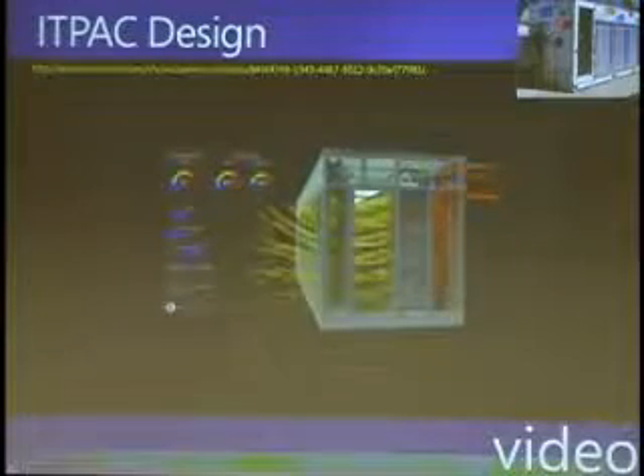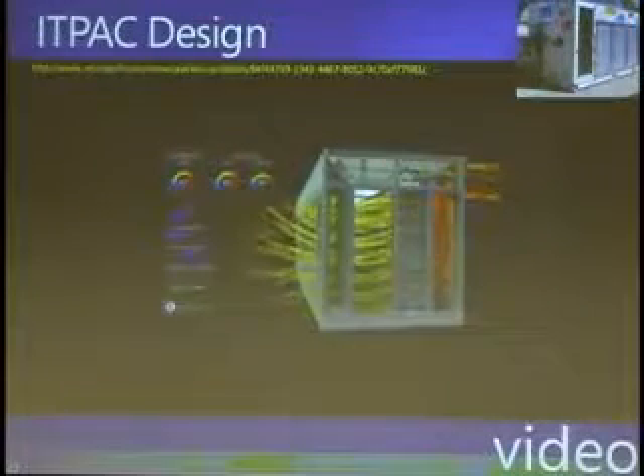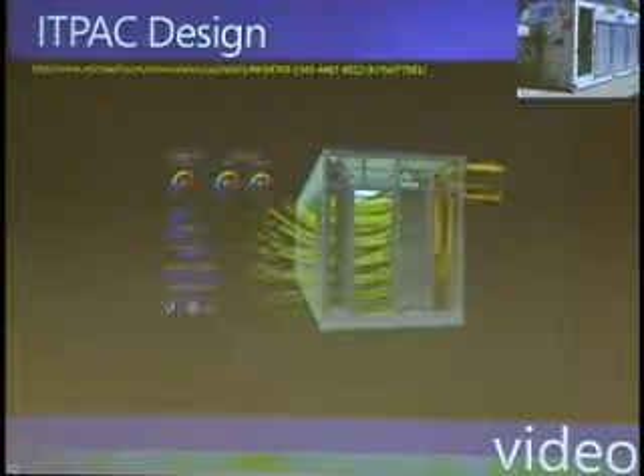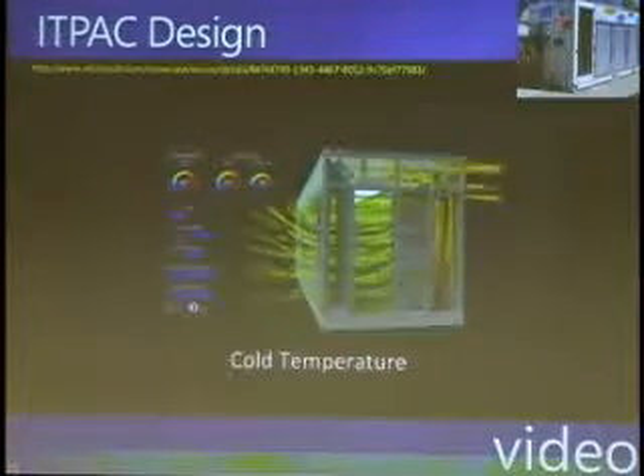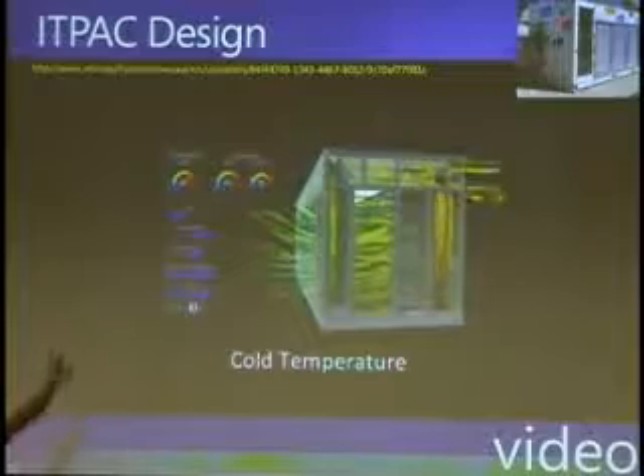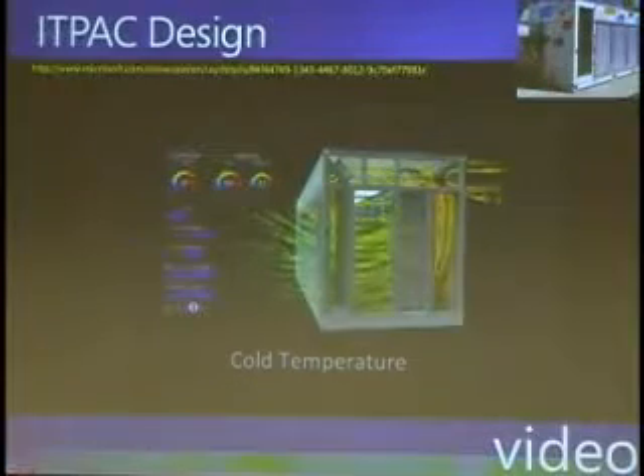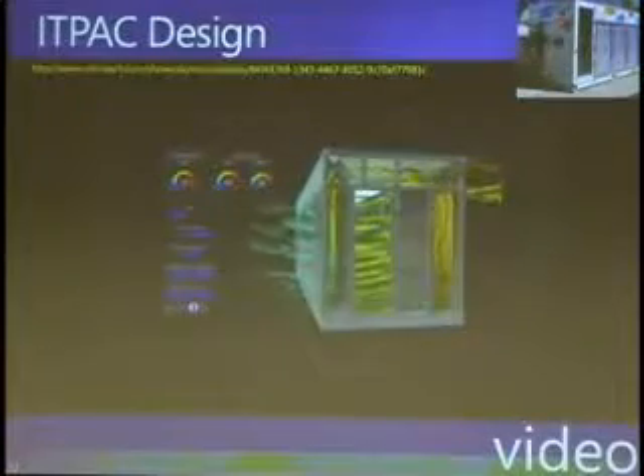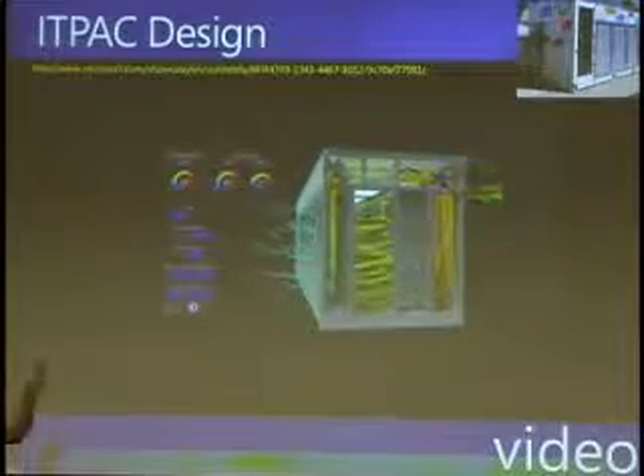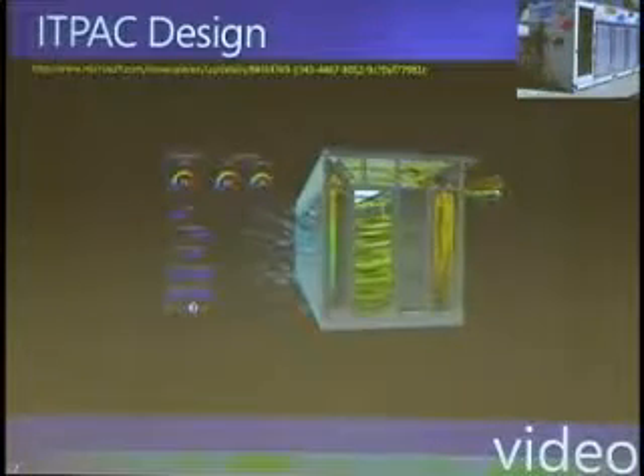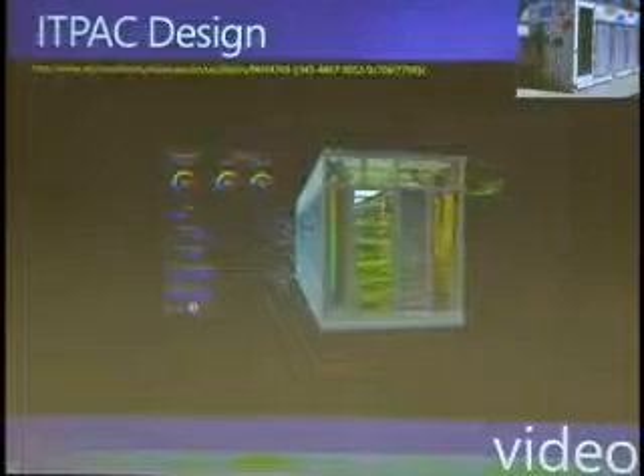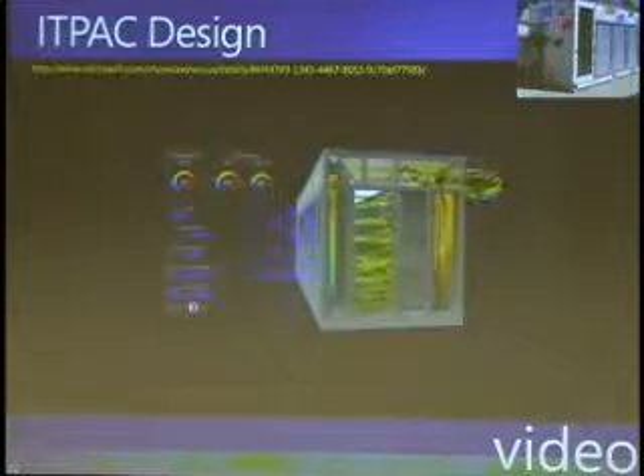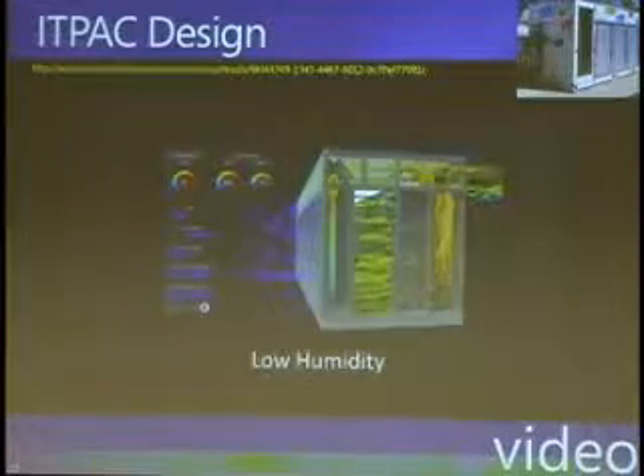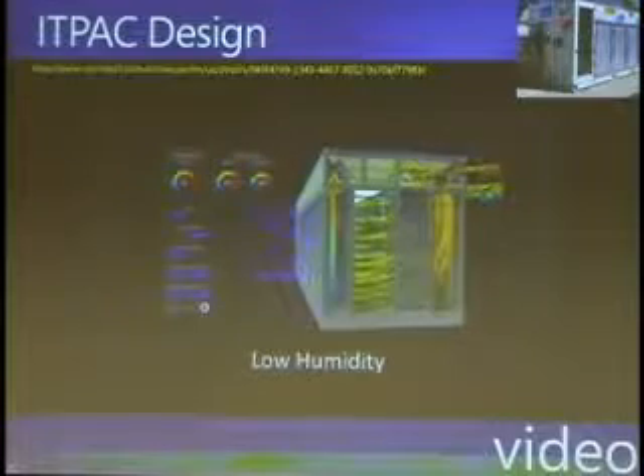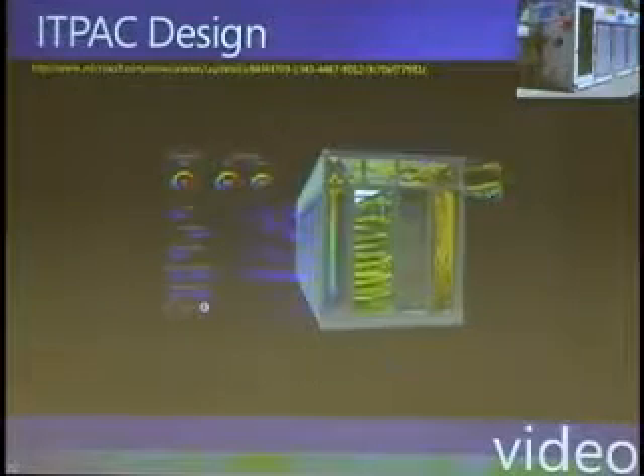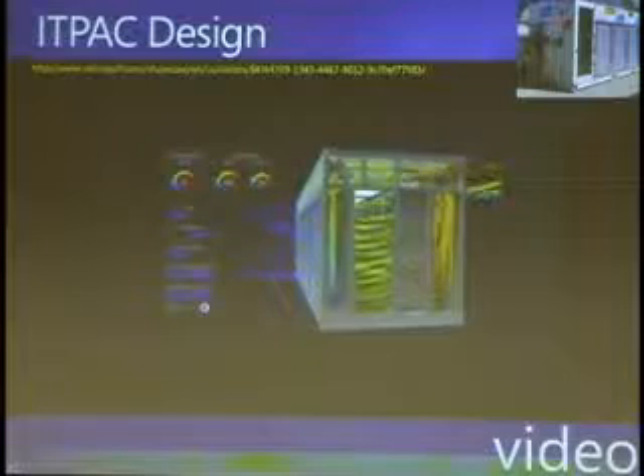Then in the winter, if it gets too cold, you start recirculating the hot air. You close the outside air a little bit, so maybe they're only open 25%, and now outside is 25 degrees, but the air going into the servers is about 50 degrees. And then if the humidity gets too low, that's not good either, so now you run the evap washers again just to add some humidity into the air.